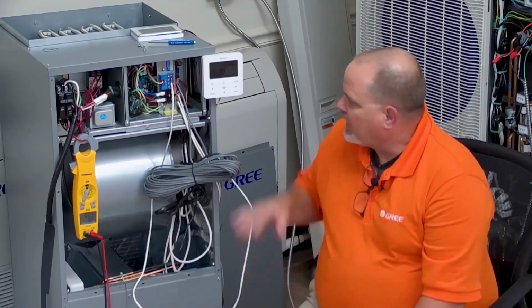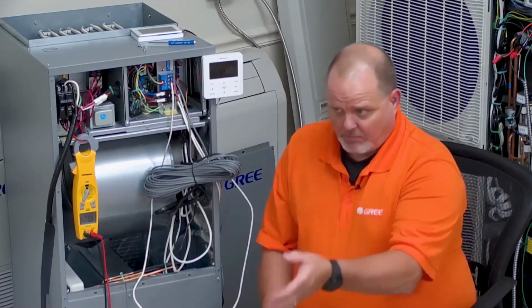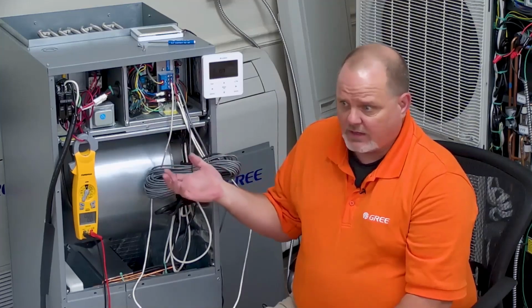So again, look for the announcements coming out. I'm hoping somewhere in October, hopefully before November, we will have these new controls available, and we'll have an announcement about that coming out real soon. So again, I don't have the part number yet or the model number of the controller. Again, these are prototypes, but we were able to get the prototype, make sure it all worked, and GREE did an absolutely fabulous job of making these controllers work the way we wanted them to control the electric heat, to make it very much like any other heat pump that I've ever dealt with in my entire career. They've always had an emergency heat function. They've always had an auxiliary heat function. And even if that heat pump was out on an error code, it shouldn't be affecting the electric heat capabilities of my indoor unit. And with this new control, we will have that.